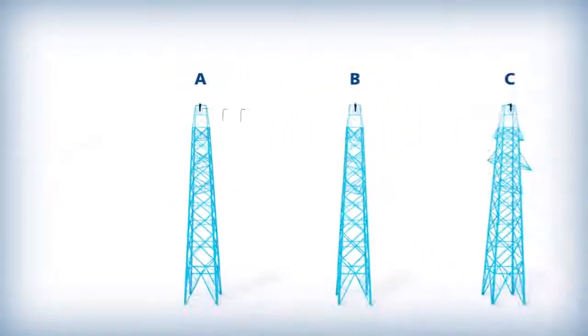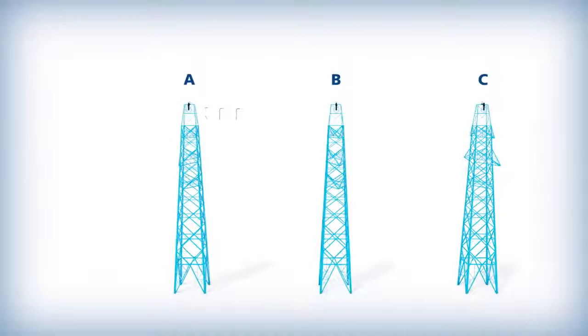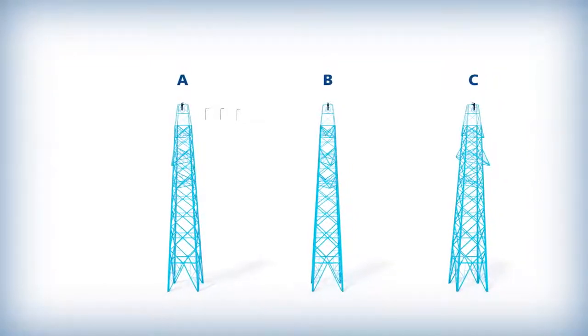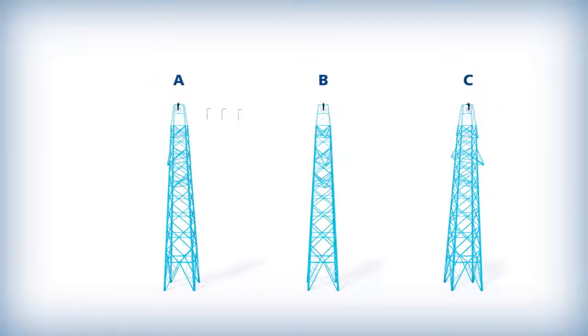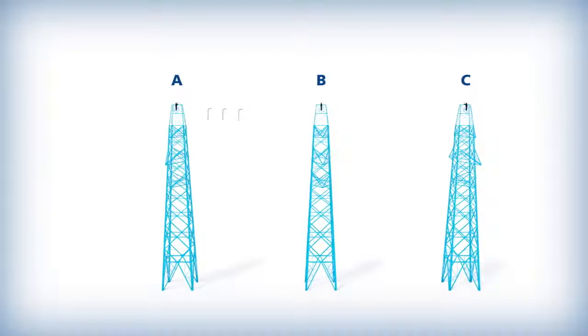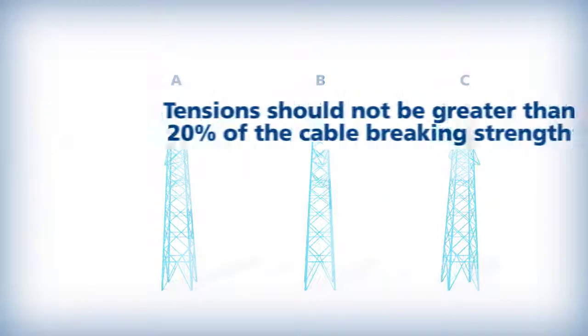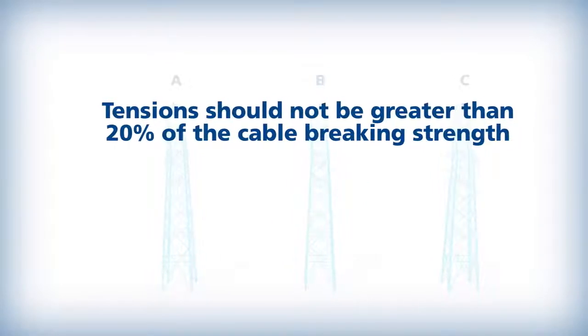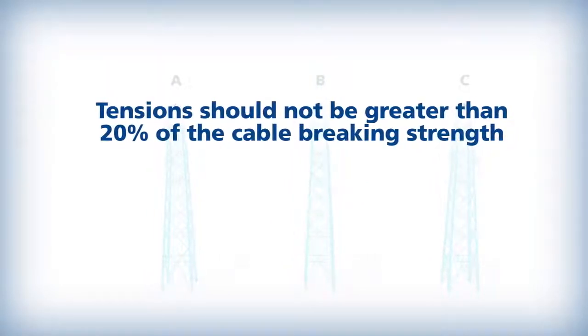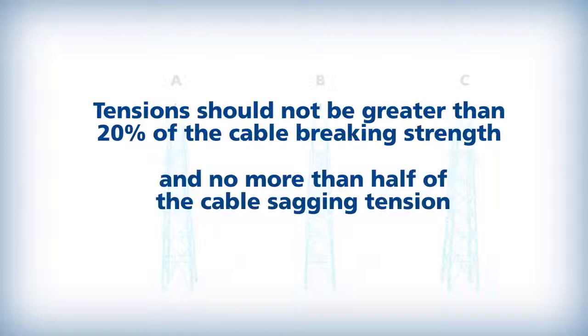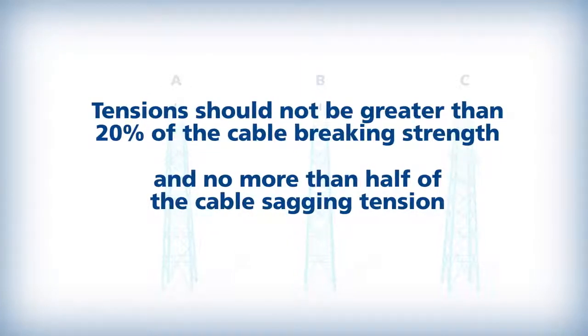The OPGW should be installed with a constant tension in order to keep the line clear of the ground or any obstacles while avoiding too much tension, as this could cause damage to the fiber units. Stringing tension should not be greater than 20% of the rated breaking strength of the cable and no more than half of the sagging tension of the cable.